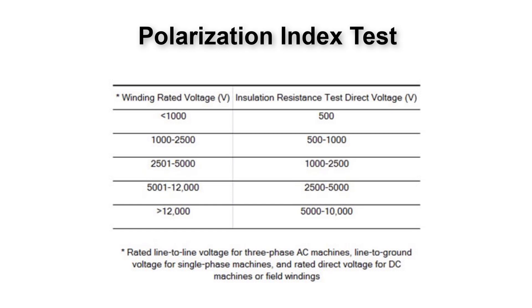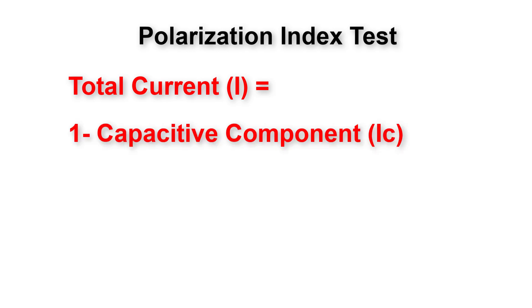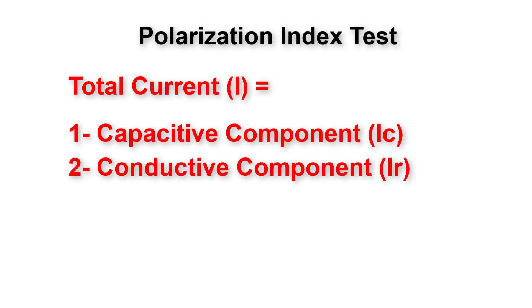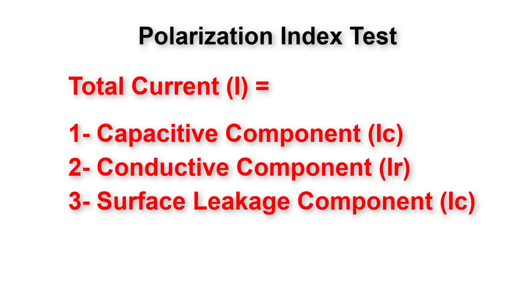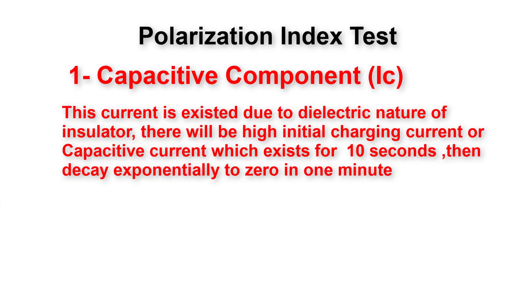Let's understand exactly what happens during the 10 minutes after applying a high DC voltage — which could be 5 kilovolts for a motor with a 6.9 kilovolt rating. There is a tiny current produced between the winding and the body in the milli or micro ampere range. This current has four main components: capacitive, conductive, surface leakage, and polarization.